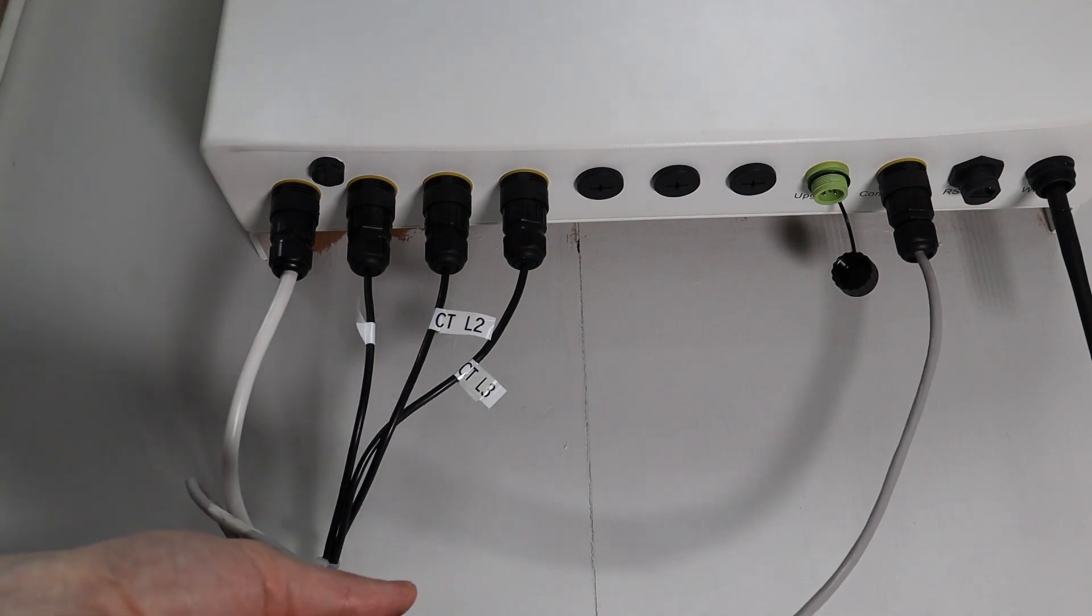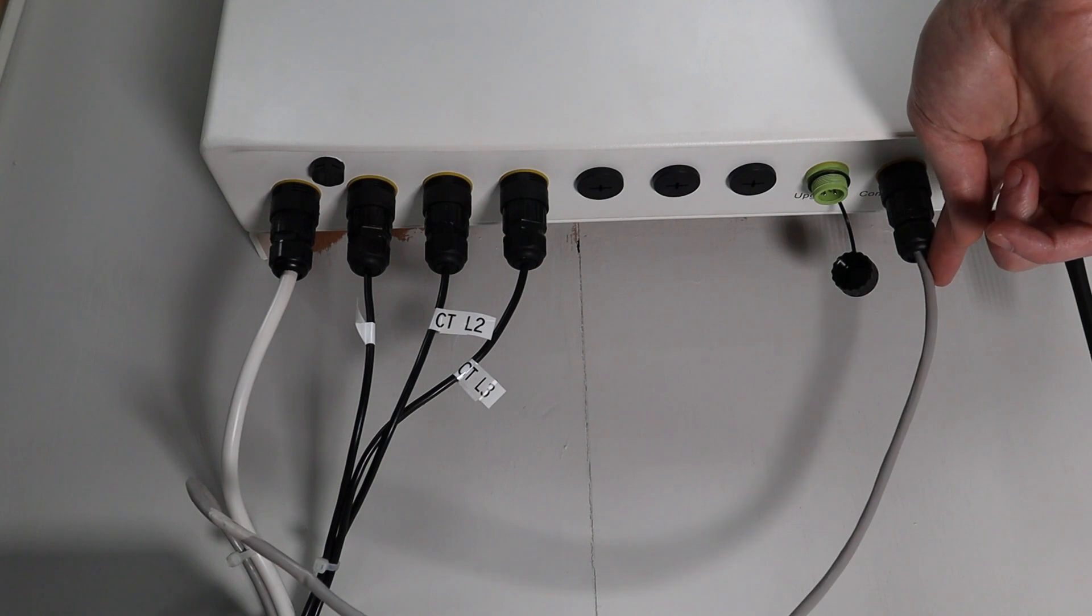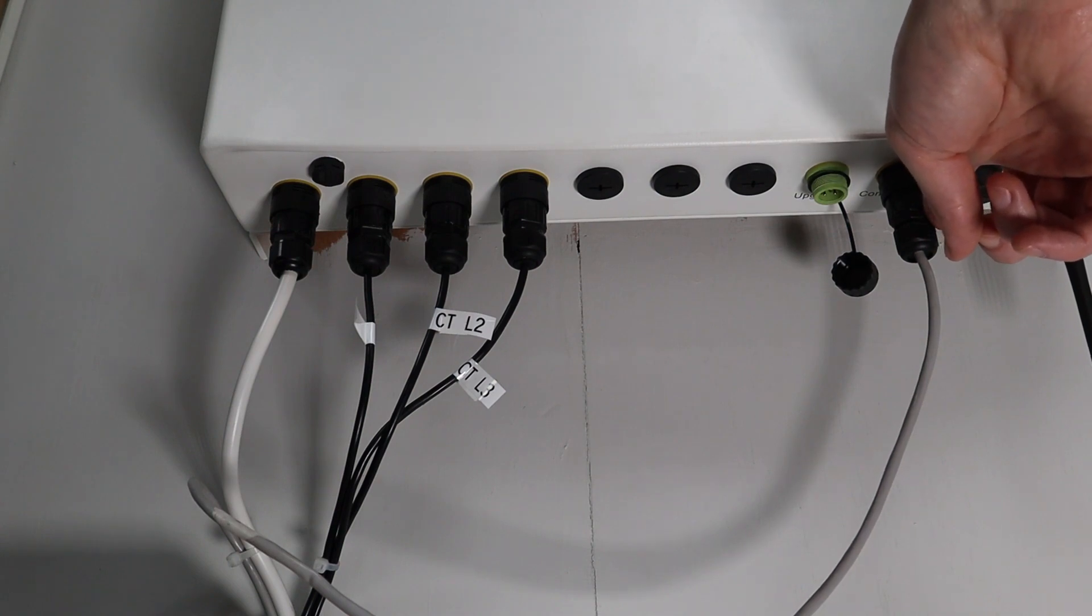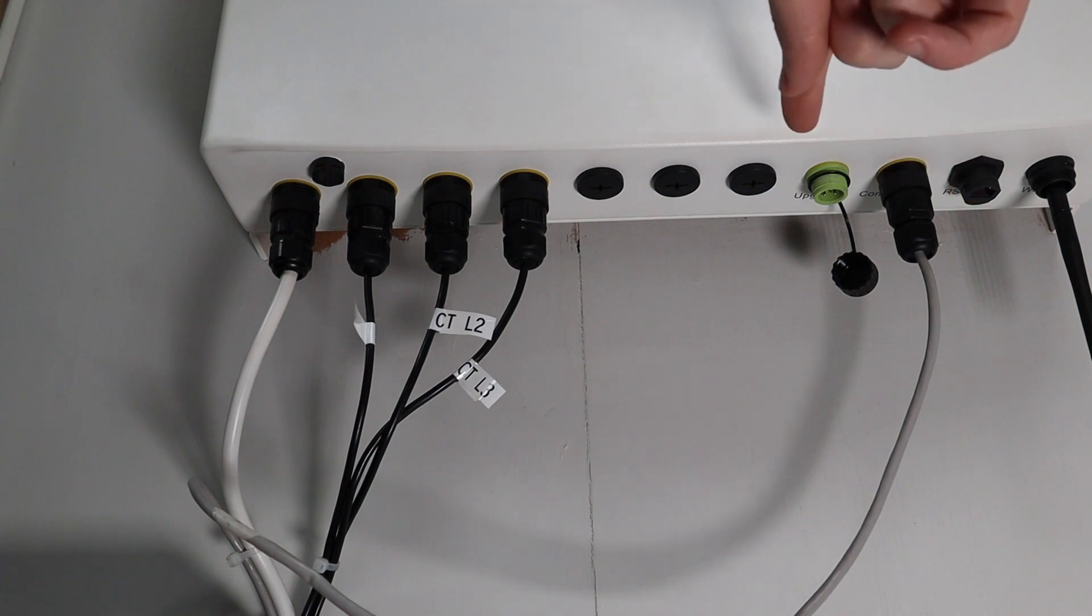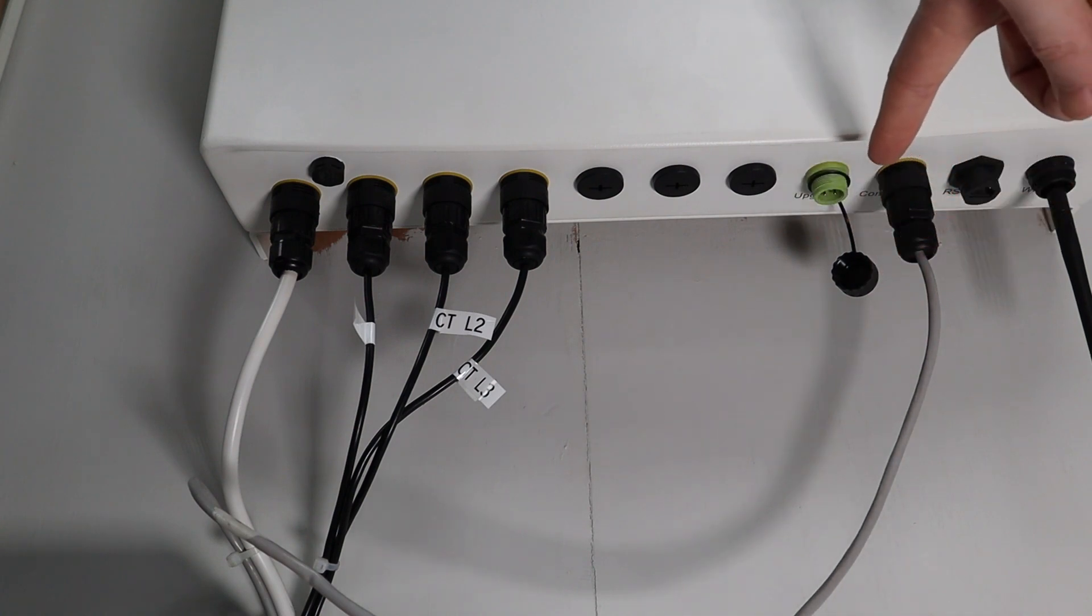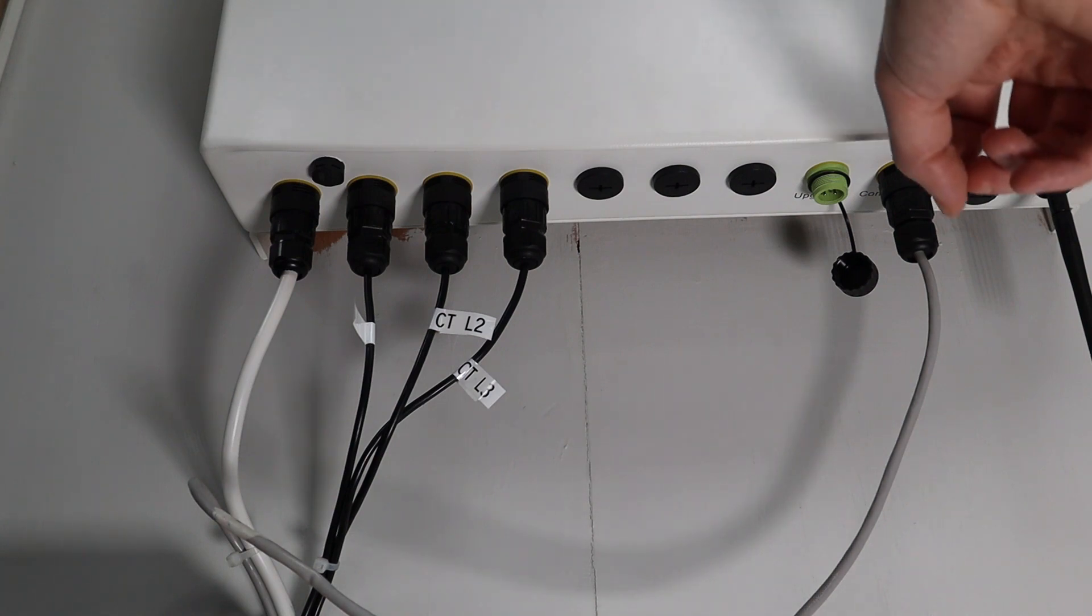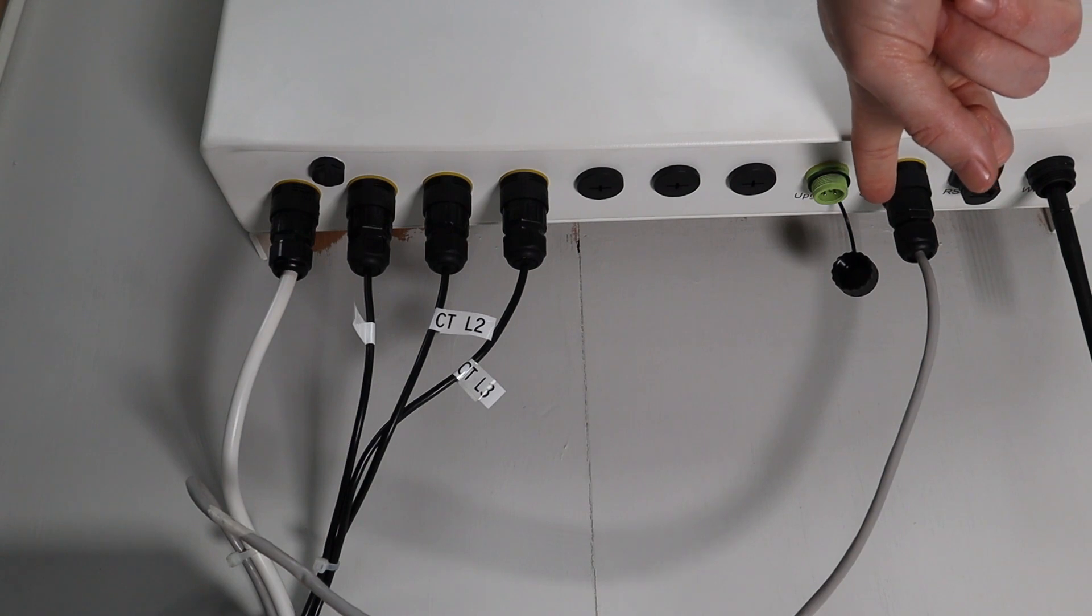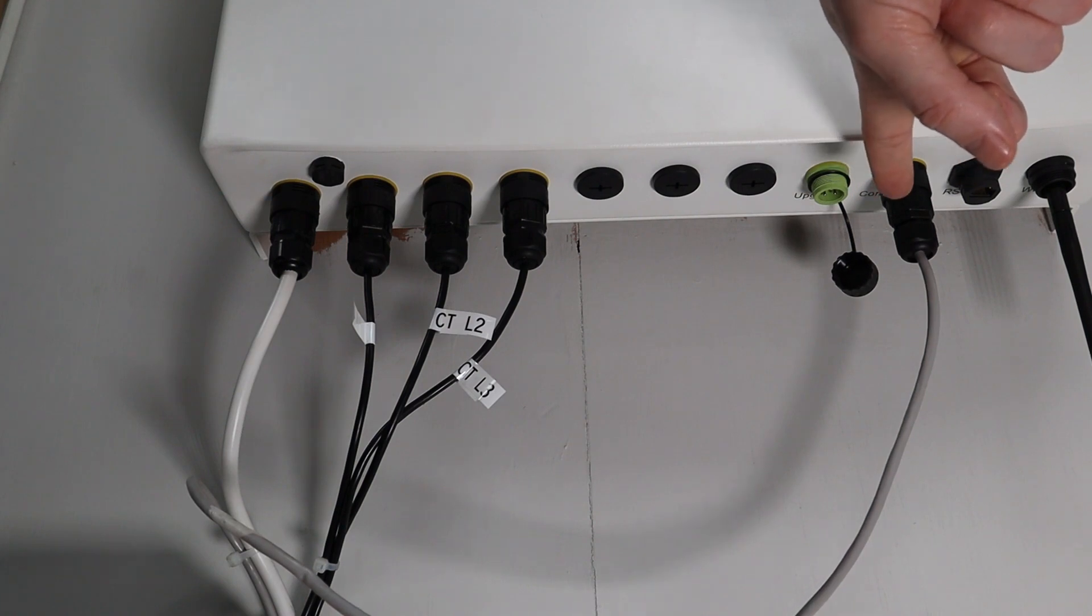And then the last thing that is compulsory to set up is setting up the RS-485 communications. The EPM needs to be able to speak to the inverters to control them. And without this cable, it will not be able to control them and the system will not work. So this is compulsory. And then some optional connections to do. So this is an EPM 5G plus, which has got an internal data logger, it does the monitoring for you. Whereas some of our other models like the EPM 5G vanilla or single phase do not have an internal data logger and you would use the four pin green plug to set up the data logger to get it online. The port name for the RS-485 is COMINV. So this is an RS-485 network for the inverters. And the port name is COMINV. INV stands for inverters.